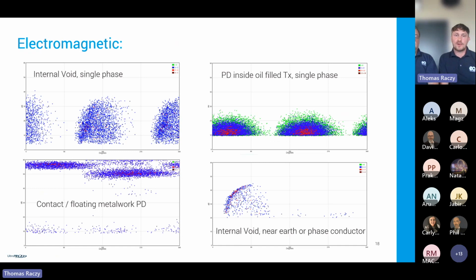In this screen, we've got very good examples of the various types of discharges mentioned previously, and you can see how very different the distribution of pulses across the power cycle is, depending on where they occur. Top left corner, we've got a typical internal void discharge, single phase, probably somewhere within the middle of the insulation, because the amplitude on both halves of the power cycle is similar. We can clearly see a leading edge which almost follows the actual sine wave as the voltage builds up and the initial discharge occurs, and loads of pulses after the leading edge, which are the aftereffect of the changes within the cavity. Every time a discharge occurs, there are physical changes within the cavity of the insulation, and chemical byproducts. So we start getting loads of different effects, and the discharge repeats again, probably within the same half power cycle, in the same cavity.